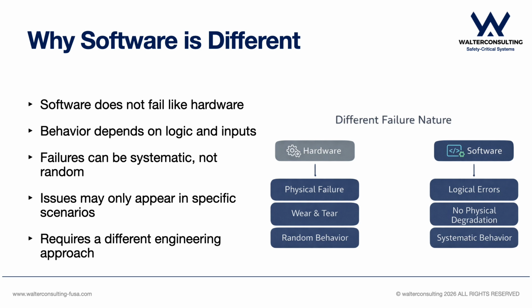Software does not degrade over time. Instead, it contains logical errors. These errors only appear under specific conditions, which means the same software can work perfectly in one situation and fail in another. This is what makes software so challenging. Failures are systematic, not random, and this is exactly why a dedicated standard is needed.